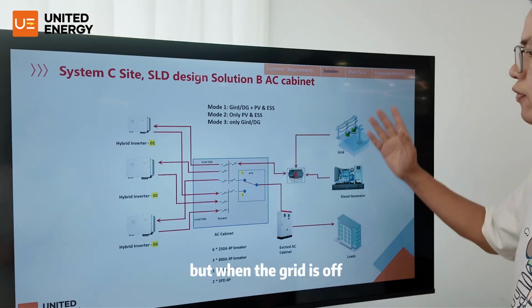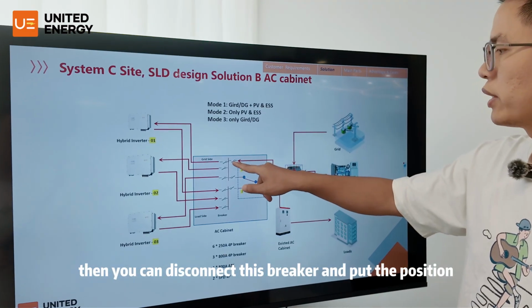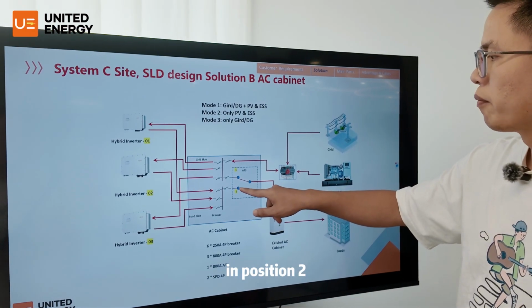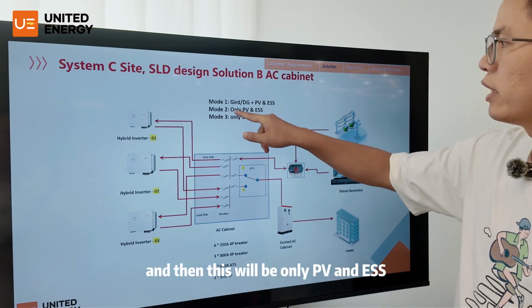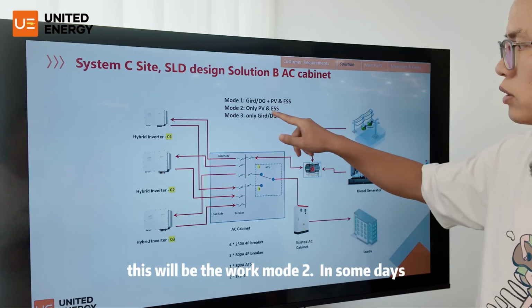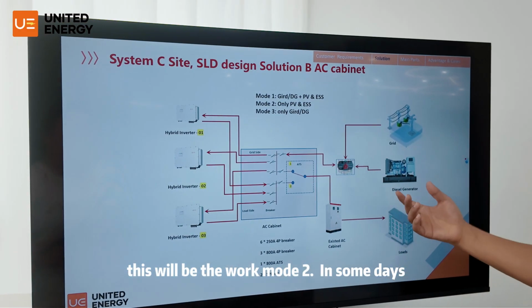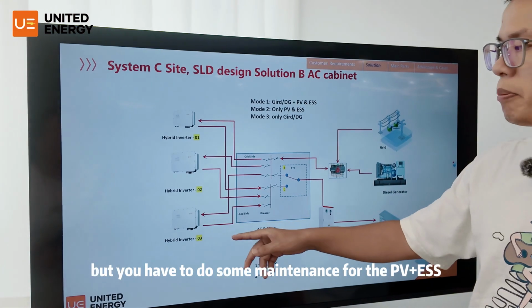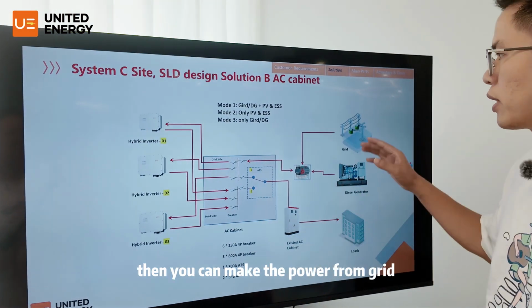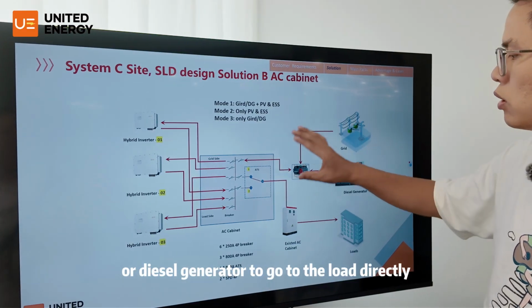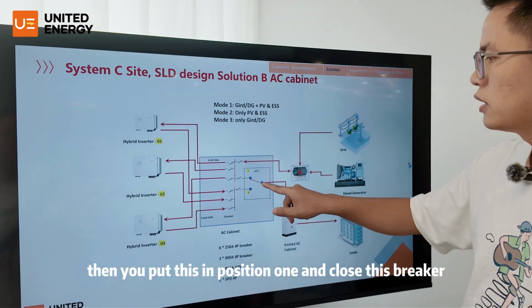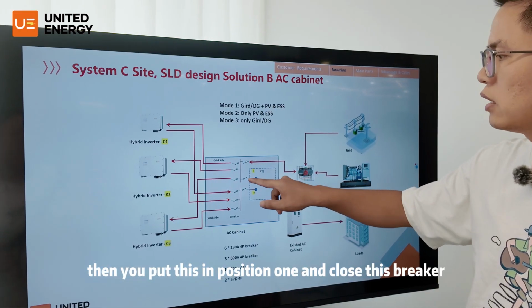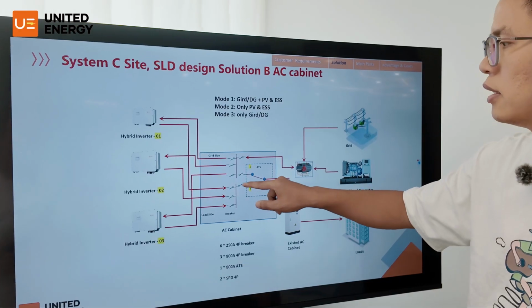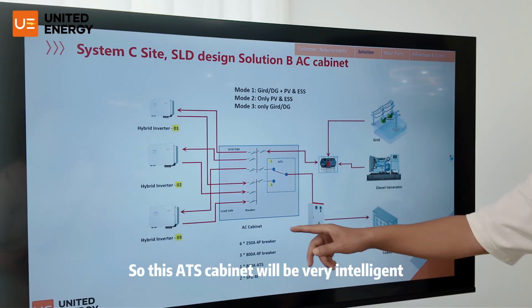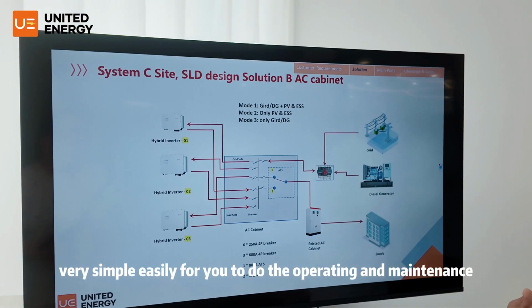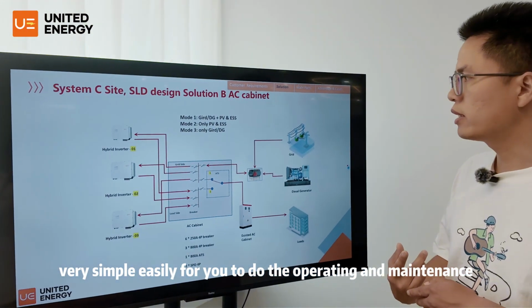But when the grid is off, then you can disconnect this breaker and put it in position 2. And then this will be only PV and the ESS. This will be work mode number 2. And on some days when the grid or diesel generator is okay, but you have to do some maintenance on the PV plus ESS, then you can make the power from grid or diesel generator go to the load directly. Then you put this in position 1, close this breaker, and disconnect all these breakers. Then you go to mode 3. So this ATS cabinet is very intelligent, very simple, easy for you to operate and maintain.